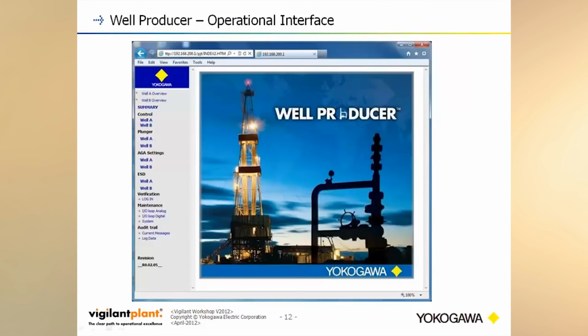We can have a couple wells, with built-in control programming like plunger lift, full electronic gas measurement or electronic flow measurement. We can do all your AGA calculations like detail, gross 1, gross 2 - all those types of methods for gas calculations. We can also do net oil computing functions, emergency shutdown, and verification and calibration logs.